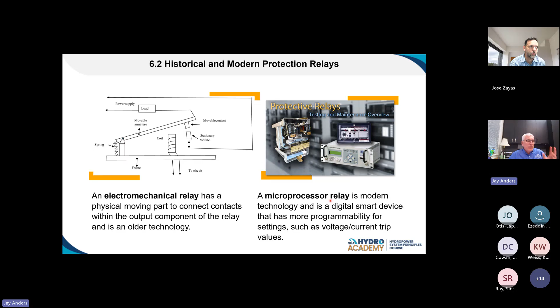It's all they are. But we're able to feed in very basic information, and these relays, because they're operating so rapidly, before the fault even gets very far down the road, before it gets very aggressive or very large, these things already see where it's going. It's anticipating functions that say, hey, in the last fractions of a millisecond, the current went up 3 amps. Well you and I would say 3 amps, that's nothing, but it did that in milliseconds. So it's able to say, if this continues for 2 cycles, we're going to be so far over current. So it trips really early. It's just amazing. I could be a geek here for a minute.